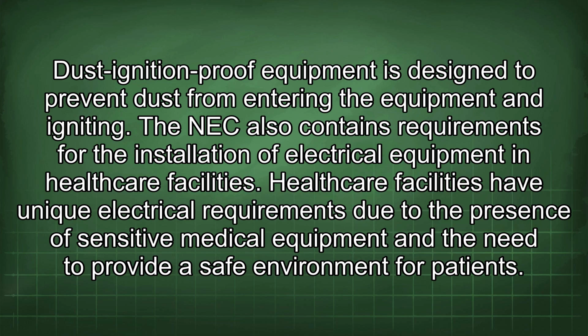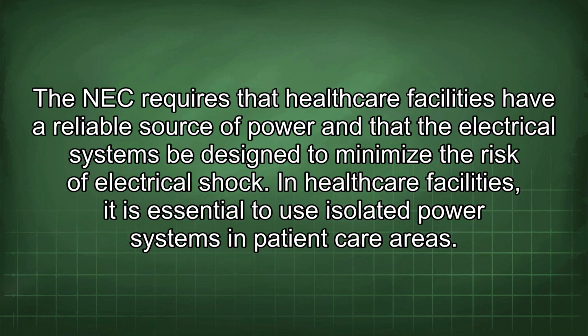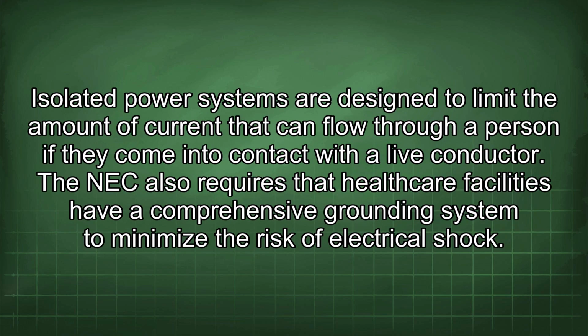The NEC also contains requirements for the installation of electrical equipment in healthcare facilities. Healthcare facilities have unique electrical requirements due to the presence of sensitive medical equipment and the need to provide a safe environment for patients. The NEC requires that healthcare facilities have a reliable source of power and that the electrical systems be designed to minimize the risk of electrical shock. In healthcare facilities, it is essential to use isolated power systems in patient care areas. Isolated power systems are designed to limit the amount of current that can flow through a person if they come into contact with a live conductor. The NEC also requires that healthcare facilities have a comprehensive grounding system to minimize the risk of electrical shock.